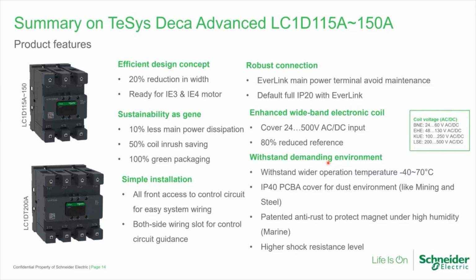This can definitely withstand very demanding environments. You can use this contactor from -40 to 70 degrees. As we mentioned, we are providing a PCBA cover with IP40 so that this can be used for mining and steel applications. We have patented anti-rust to protect magnets, and this contactor can very well be used for high shock resistance levels.